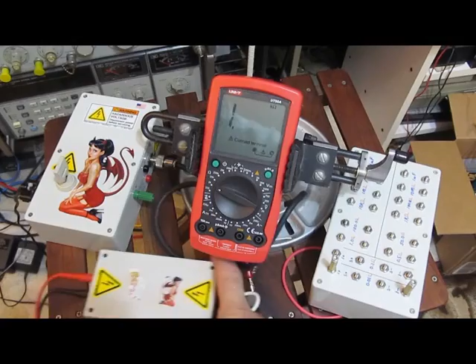This is our attenuator, and for the testing we're going to run, the generator is now set at essentially 6,000 volts. This box is now going to protect this meter against this. This meter would never withstand this kind of voltage.